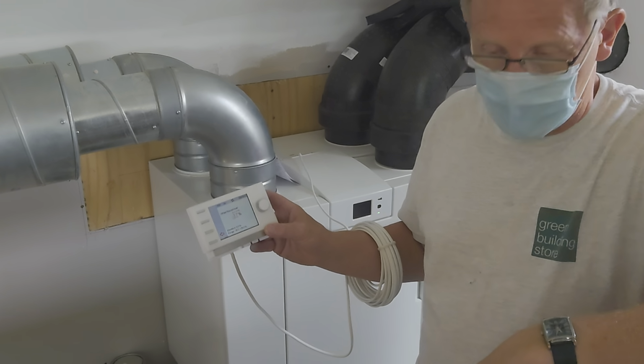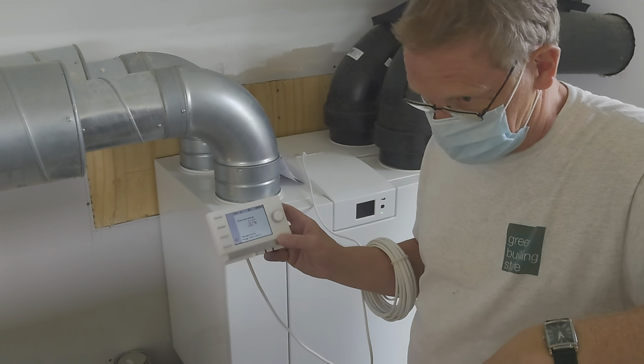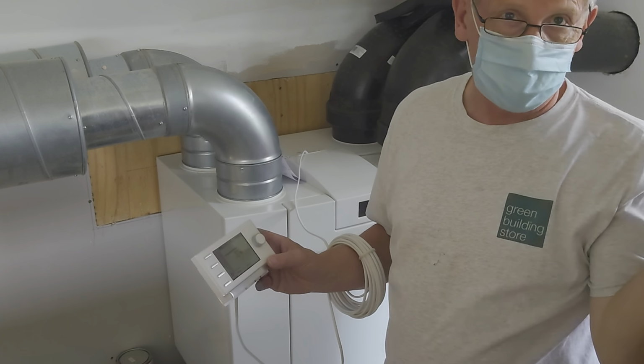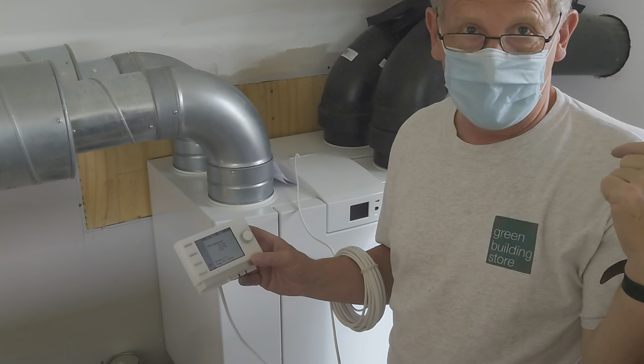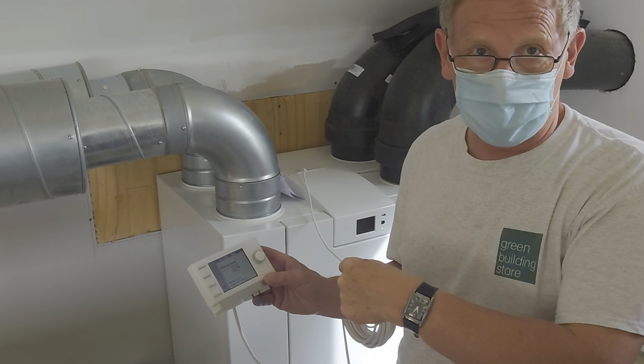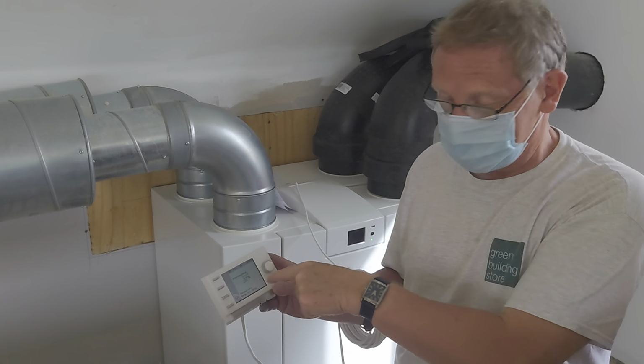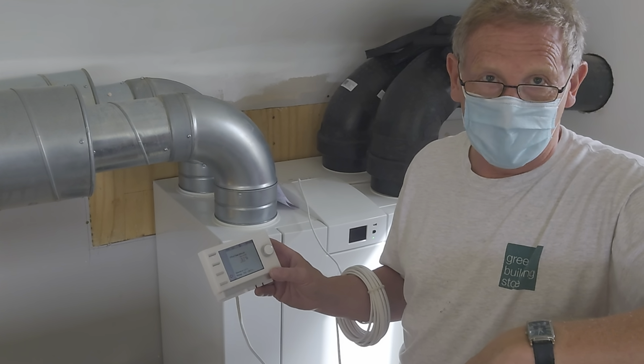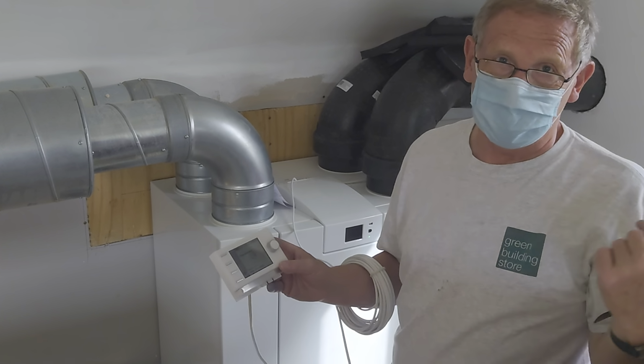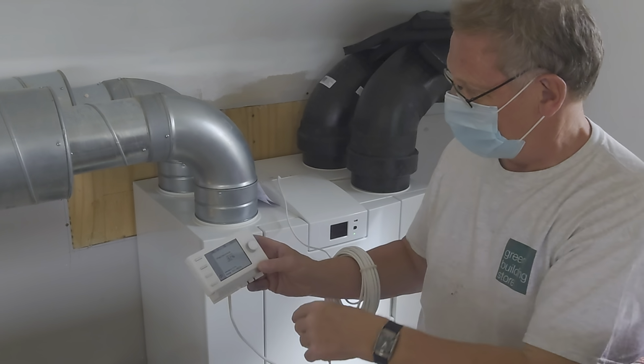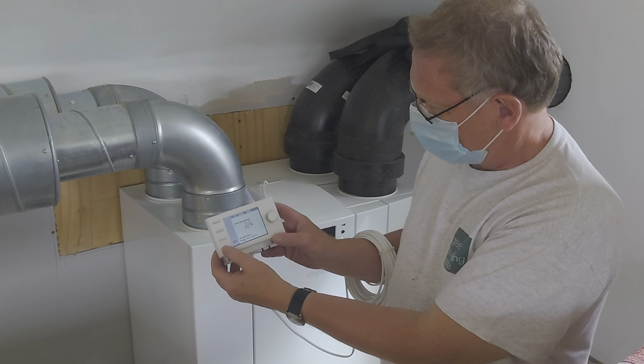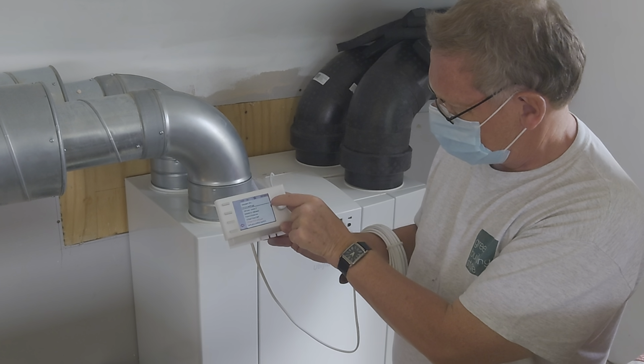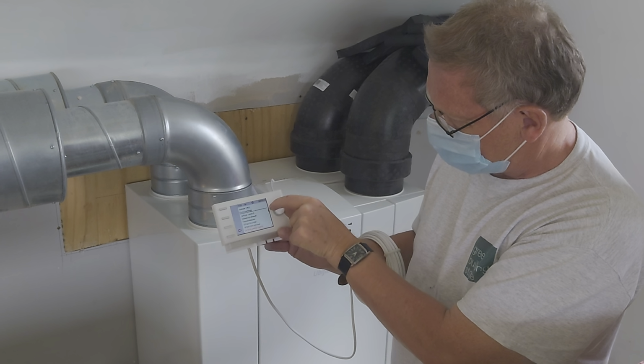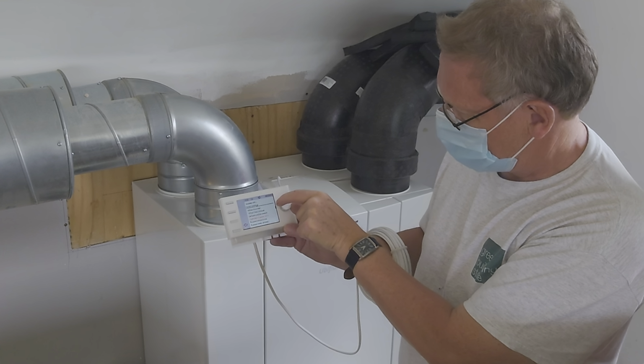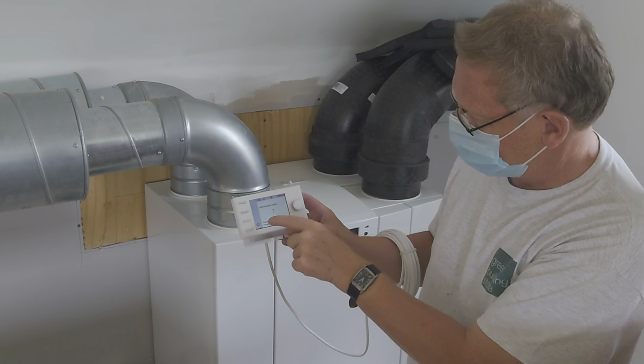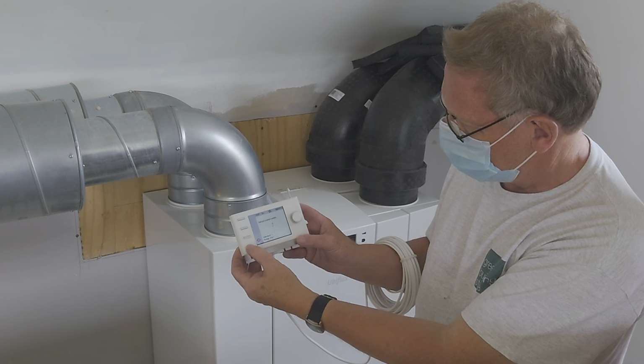Okay. I work on the assumption that my £1,500 meter, annually calibrated, is more accurate than the £20 pressure sensors inside the machine that tell the machine what to do. I work on the assumption that I'm right and the machine's wrong. Yeah, that makes sense. So back on that, default position switch, I can't remember what that is without looking in the manual, but it's set to its default setting of 1.